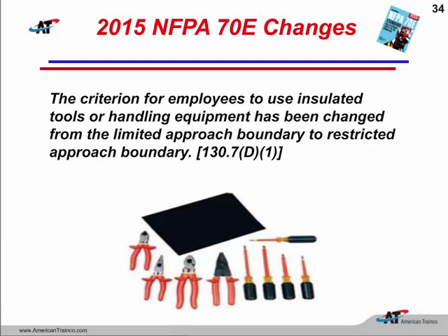Okay. They also changed the requirement for 1,000-volt rated tools. This has been changed to the restricted approach boundary in 2015. If we entered the limited approach boundary, which was at 42 inches, and it still is at 42 inches for most of our equipment, then we had to have 1,000-volt rated tools in our hand. But in reality, that limited approach boundary was really to take a visual look at something. It really wasn't to go in and interact with that equipment too much.